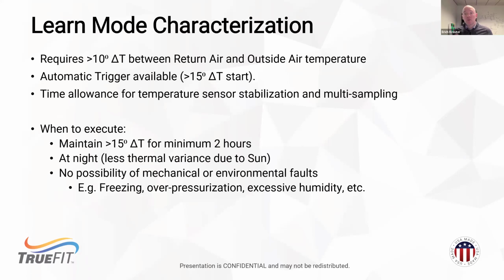A little bit more on the learn mode, and then we'll give you an example of what that means very simplistically on that rooftop diagram. But we do want to see a delta T between return and OA in order to guarantee best accuracy. 10 degrees is the minimum, 15 degrees is better. And again, we want to make sure we maintain that delta T for approximately 2 hours.